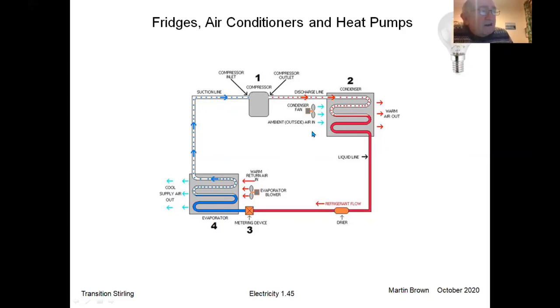And these two can swap over very easily simply by reversing the action of the compressor. That's why if you buy an air conditioner unit, it's also got a warming setting on it. The key point about heat pumps is that for every kilowatt of power that you put into the compressor, you get 2 or 3 kilowatts of heat out. And that's more than 3 kilowatts of heat actually these days. And that's not true of a straightforward heater that you have in your house. You put in a kilowatt of electricity, you get a kilowatt of heat out. Not so with a heat pump. That's why heat pumps are considered much more environmentally friendly, and why they obviously use a lot less power for the same amount of heat, basically.